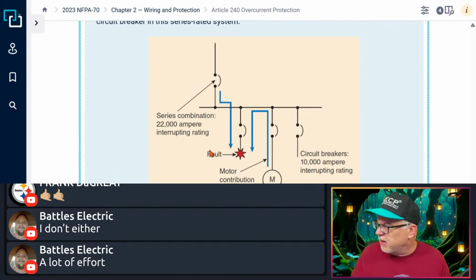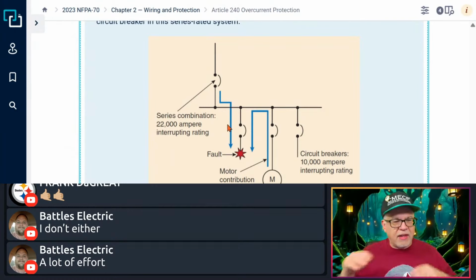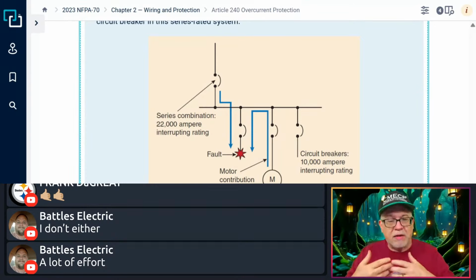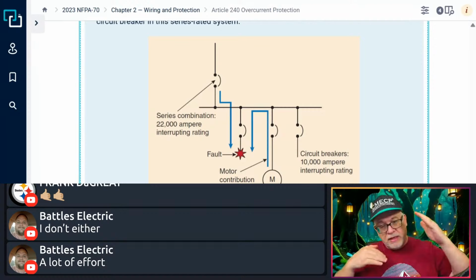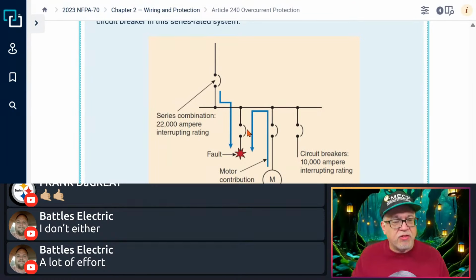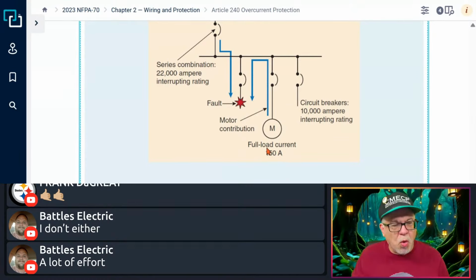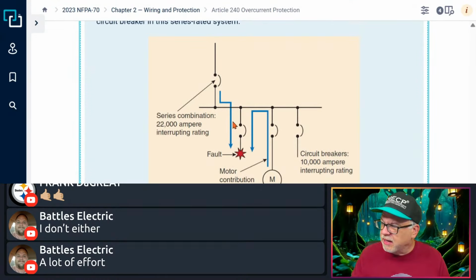So again, this circuit breaker right here is 10,000 amps rated. We'll assume these are as well. This one right here faults right here, and this is just showing you the whole layout, by the way. The motor's coming in through here. So you have to look at the other circuit breakers on the system, and if there are any breakers between it and the fault, there are other circuits right here, you have to make sure that this motor's FLC, which in this case is 150, is not more than 1% of the rating of any of these circuit breakers.